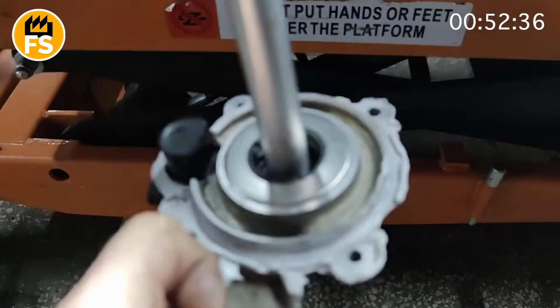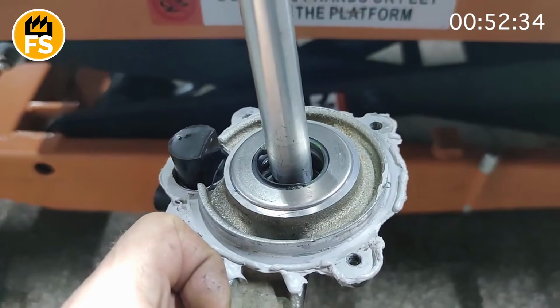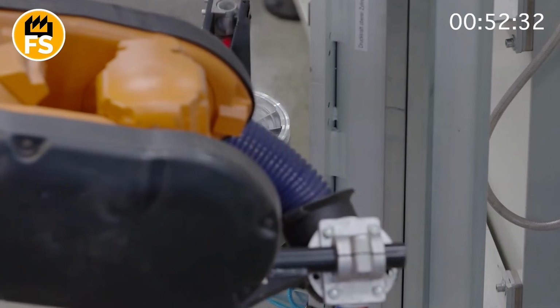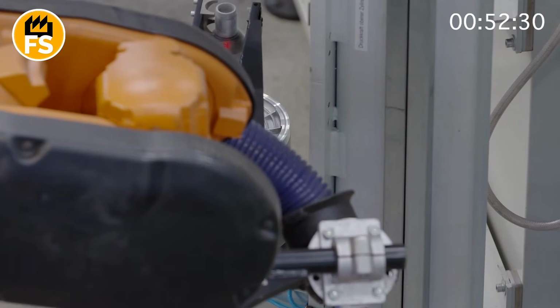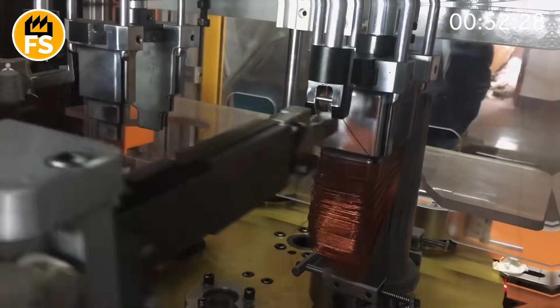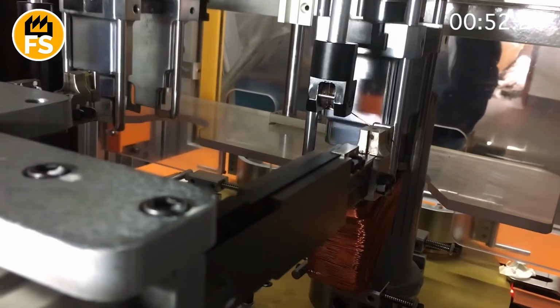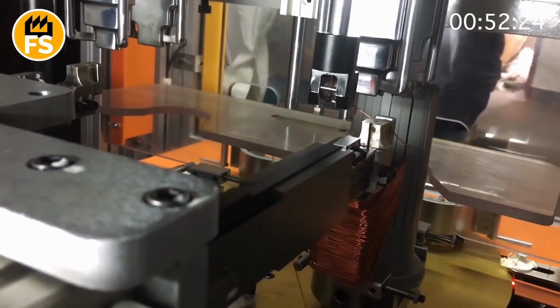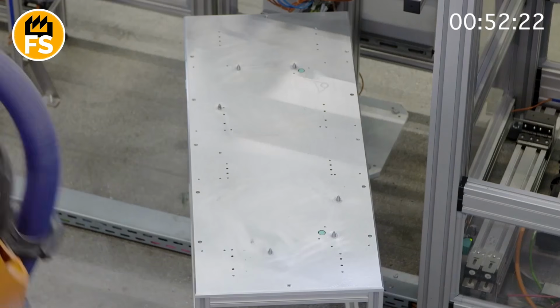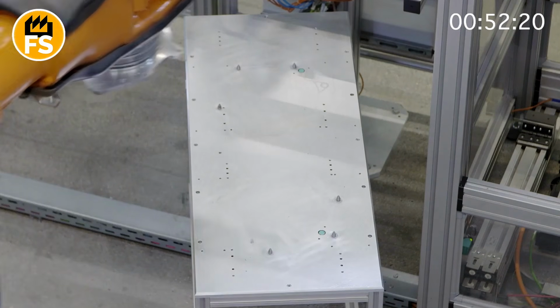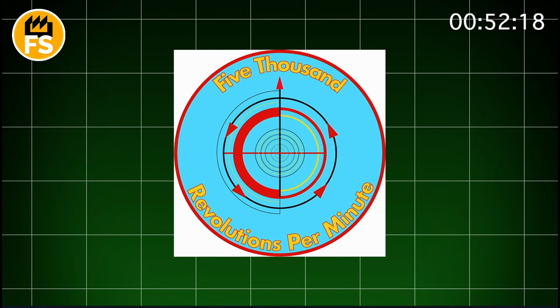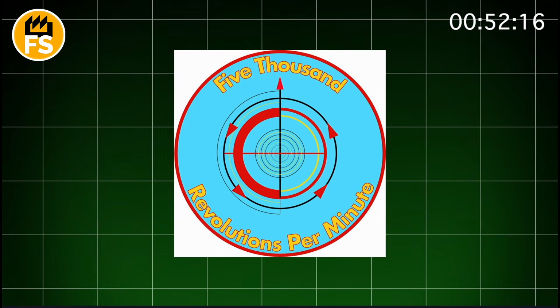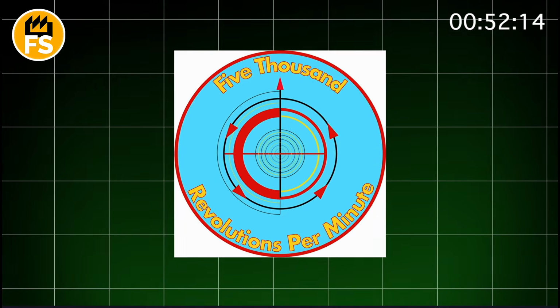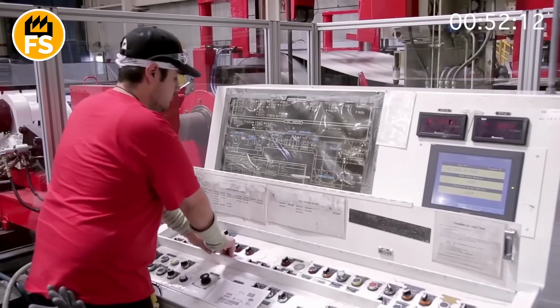The rotor windings are then connected in a specific sequence: star, delta, or another type of connection. Everything is secured, insulated, and sometimes varnished. The insulated ends are led out to slip rings or brush assemblies, depending on the design. After this, the rotor is balanced, as it has to rotate at speeds of thousands of revolutions per minute. Any extra 100 grams on the edge, and everything will vibrate, hum, and heat up.